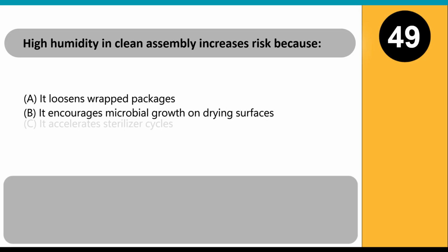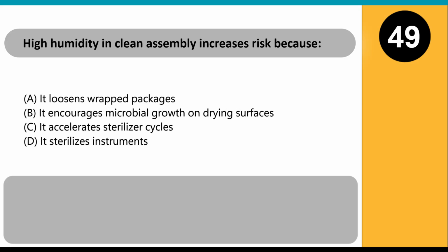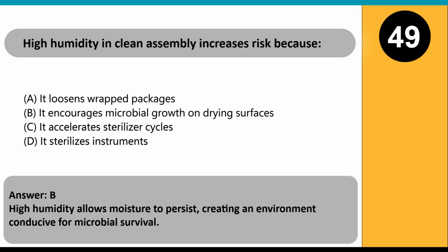High humidity in clean assembly increases risk because: A. It loosens wrapped packages. B. It encourages microbial growth on drying surfaces. C. It accelerates sterilizer cycles. D. It sterilizes instruments. Answer B. High humidity allows moisture to persist, creating an environment conducive for microbial survival.